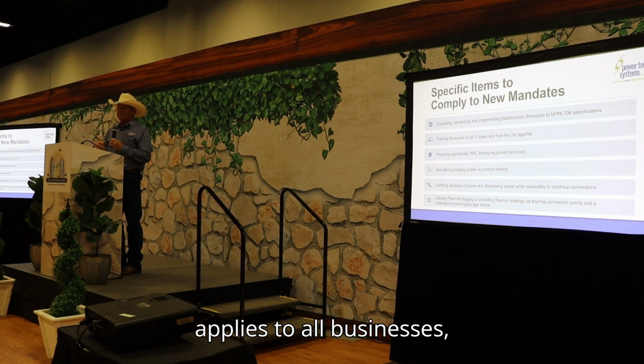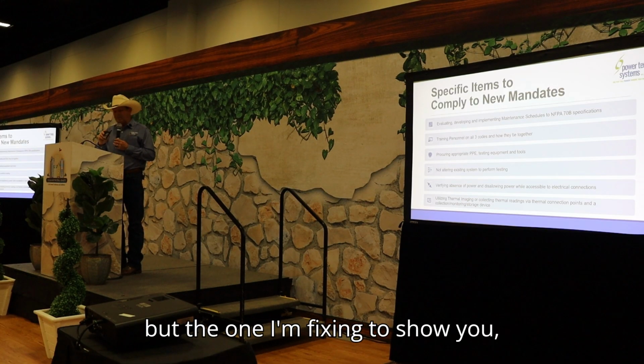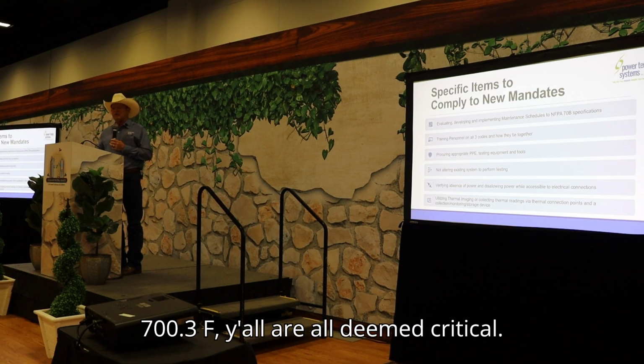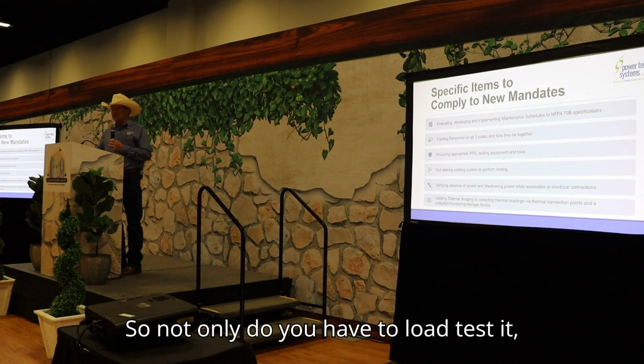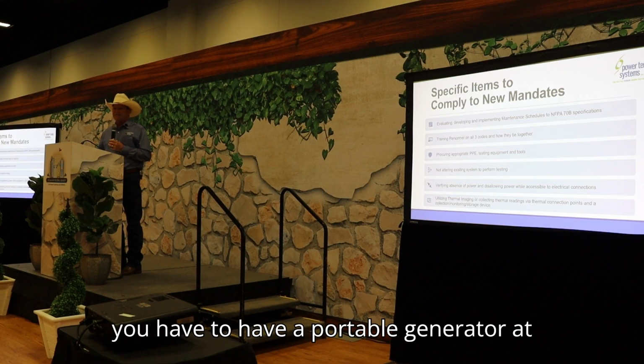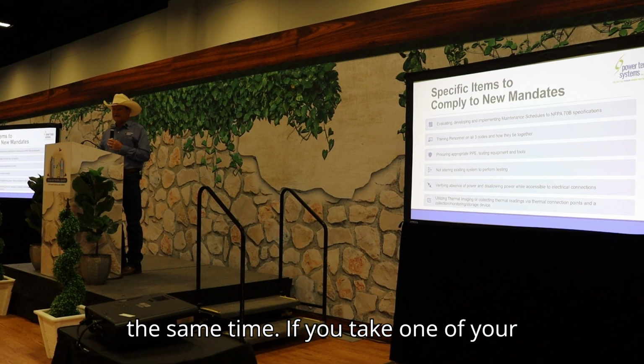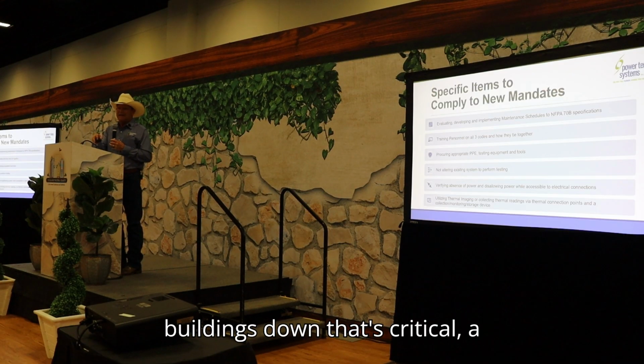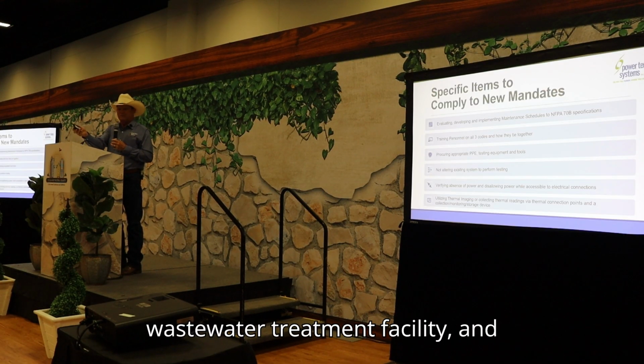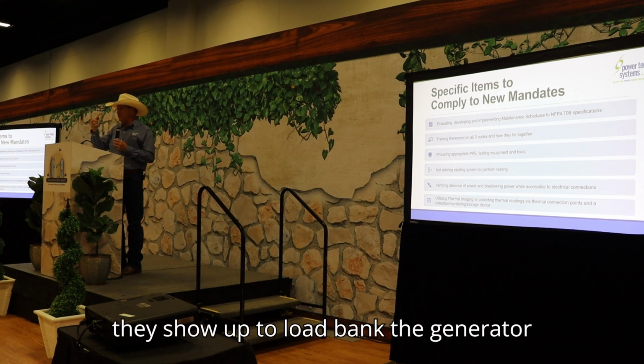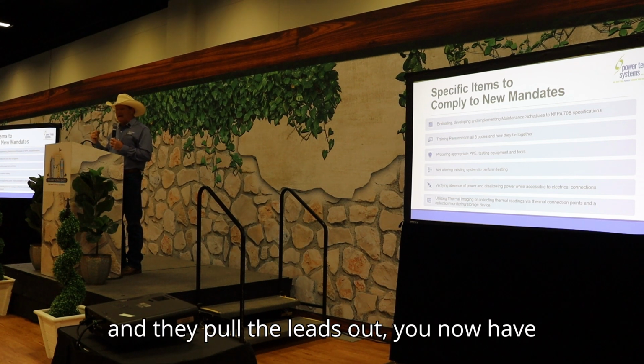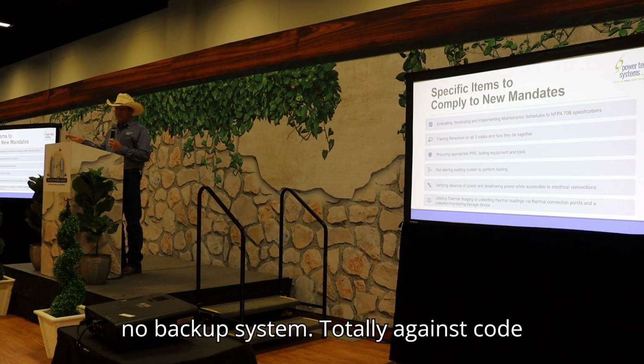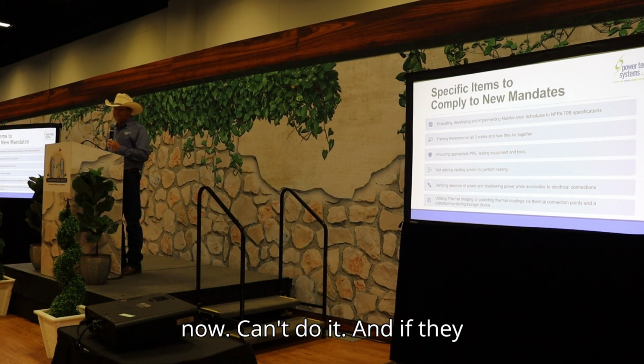So this applies to all businesses, but the one I'm fixing to show you, 700.3, y'all are all deemed critical. So not only do you have to load test it, you have to have a portable generator at the same time. If you take one of your buildings down that's critical, like a wastewater treatment facility, and they show up to load bank the generator and pull the leads out, you now have no backup system. That's totally against code now. Can't do it.